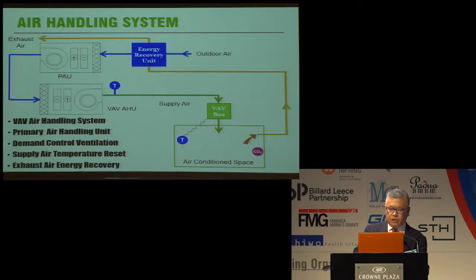Hospital also requires a large amount of outside air to maintain a very high air change rate for acceptable indoor air quality and offset the exhaust air in order to maintain building pressure. The high humidity and temperature of Hong Kong weather impose a tremendous cooling load in conditioning the outside air.